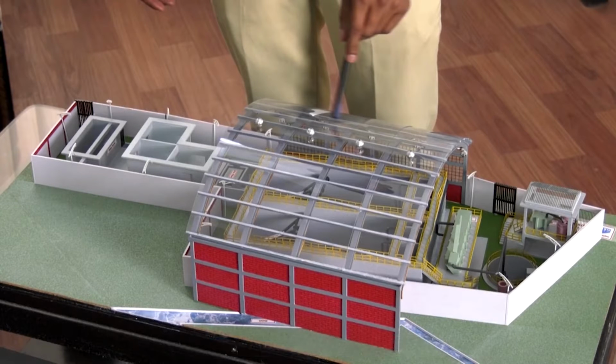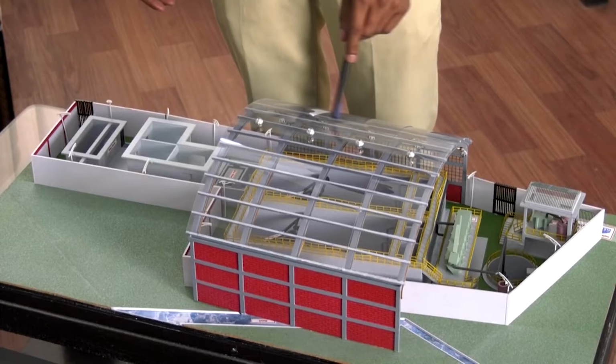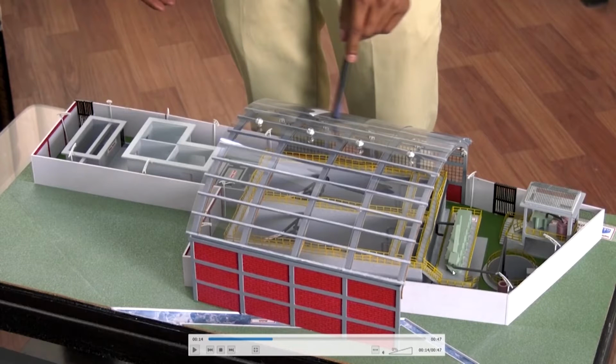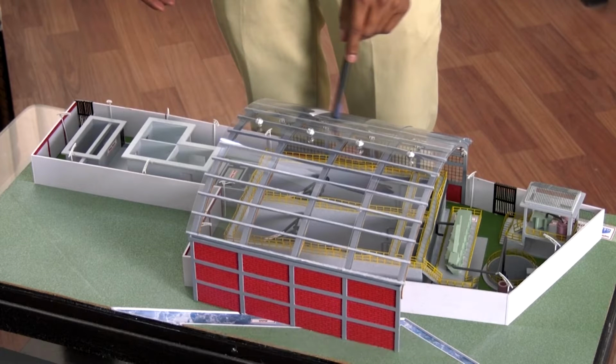And why is it at the lowest level? In IIT Roorkee, the sewerage network flows by gravity, as is the case in most other places. So, the end point will be pretty low, and then as we discussed, you will have pumping or headworks or such, and here we have a submerged pump that is lifting the water up to this particular treatment unit here. Here we have the coarse screens and grit removal, right? And from here the water goes to these sequential batch reactors. We have two sequential batch reactors, reactor 1 and reactor 2. And here you see some tanks out here. These are the bioselector tanks, or bioselectors.